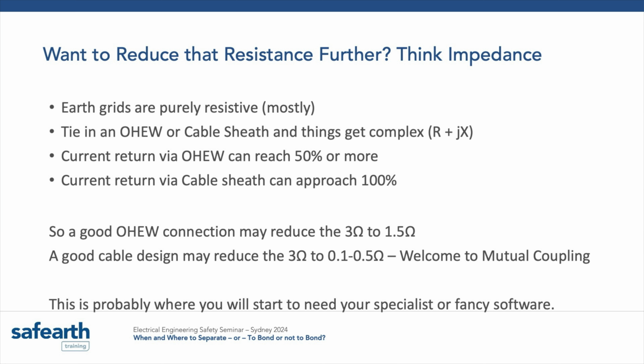You know, it's crazy. But an overhead earth wire, earthed well along its route all the way back to its source, will carry about 50% of the fault current back. A really well-designed cable design with good quality sheaths, bonded properly, bonded at each end, will approach 100% of its fault current return. Now, I know that might sound crazy, but I'll give you an example of why that has to be the case.